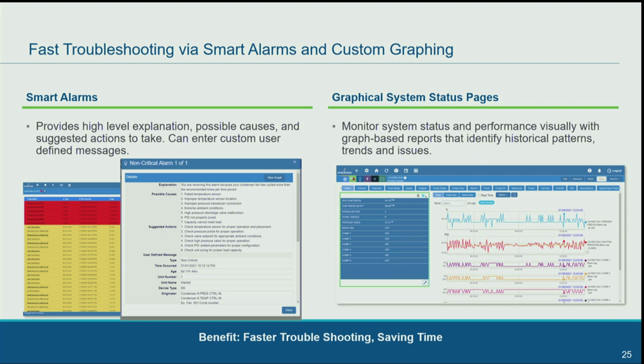This is looking at a suction group for my medium temp suction group. So say I want to look at my gas cooler outlet temperature or fan speed—I could go to another application and bring it into this graph. So there's a lot of flexibility there; just hit points view to add or subtract points.